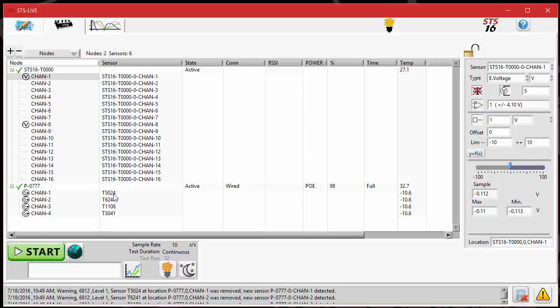They're all tilt gauges. It was able to recognize the name of these tilt gauges and pull in the calibration factor associated with these. So I can check that by clicking on the channel that I'm interested in. I can see that it now has this sensor T5024. It's a rotation, and it pulled in the calibration factor here of 0.354 radians. So this node is ready to run a test.